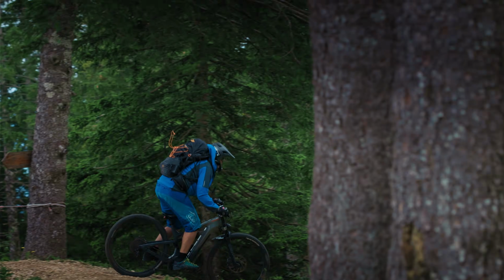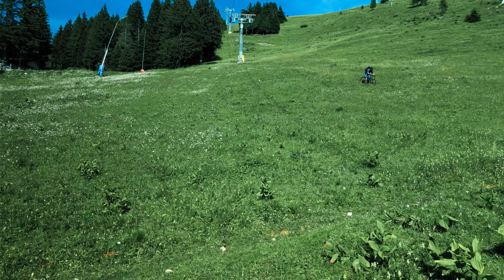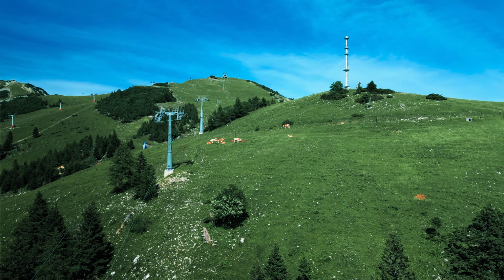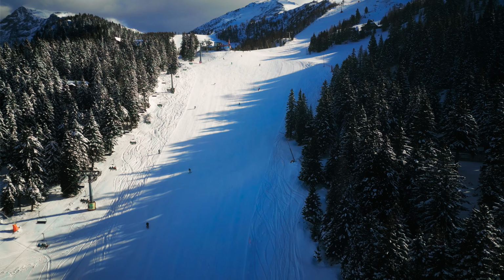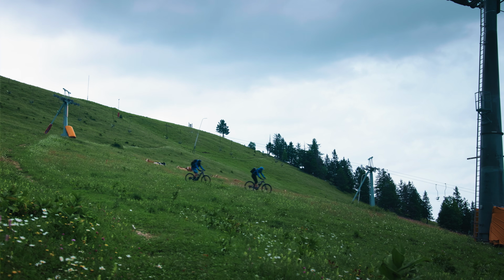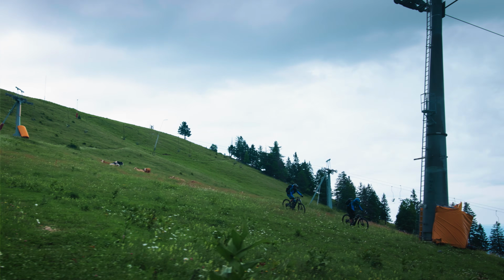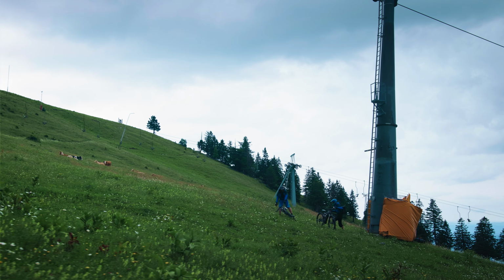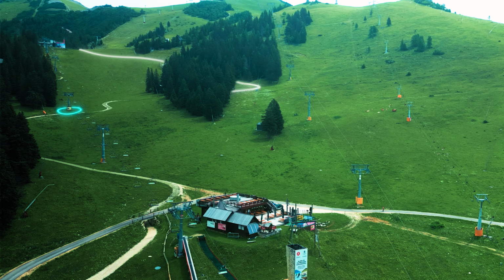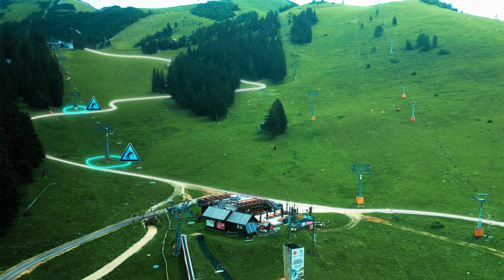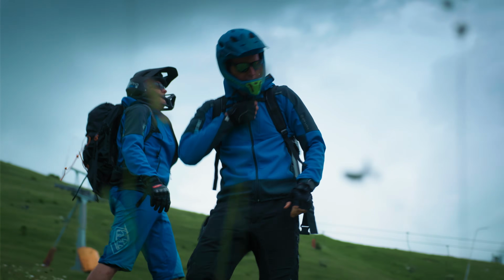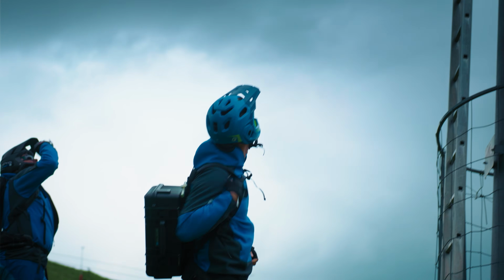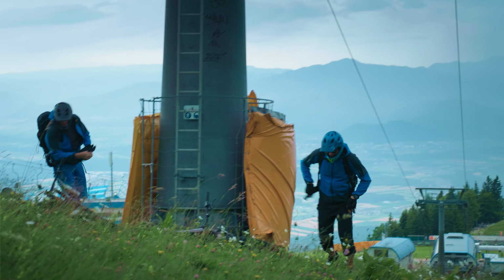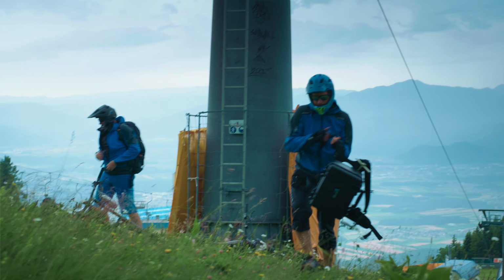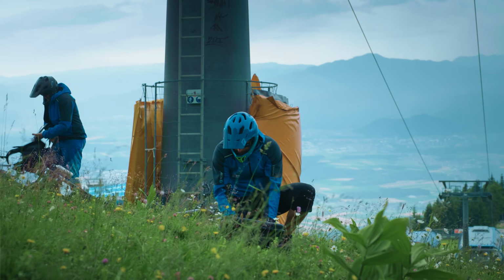These installations may offer shelter during storms, but caution is needed because most grounding systems were designed for winter operation when snow provides natural insulation. During summer, the risk increases significantly. Without snow or protective clothing, people and animals near these systems are more exposed. This is why it is essential to test for touch and step voltages. These measurements reveal hidden dangers caused by aging, corrosion, material washout, or installation errors. Neglecting protective measures can be fatal.